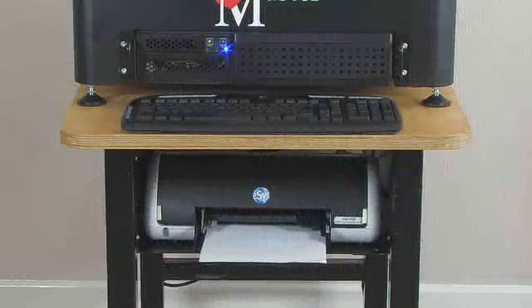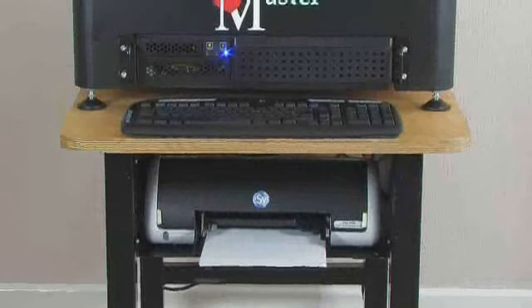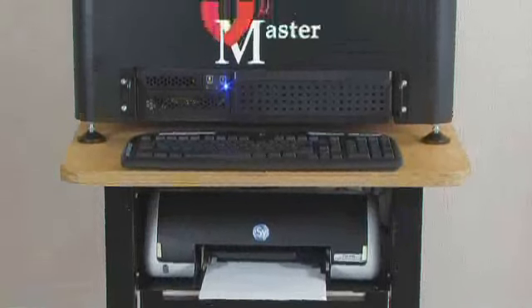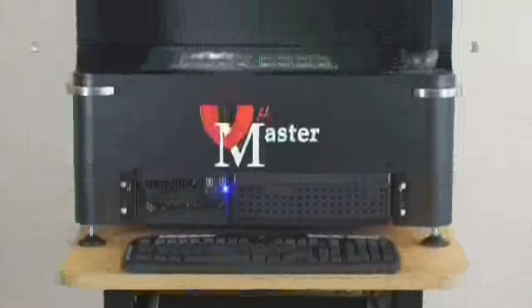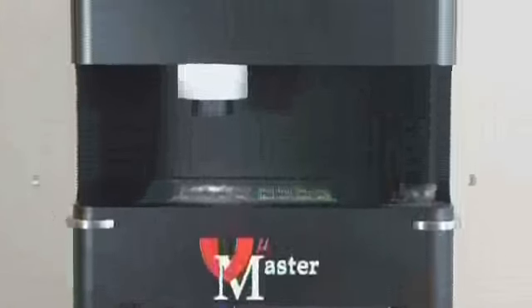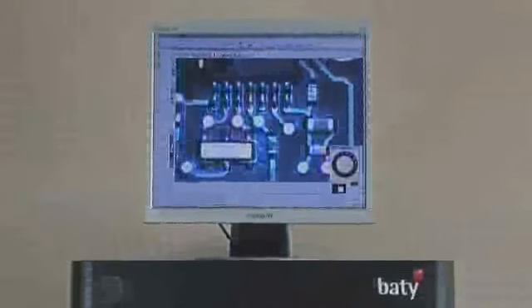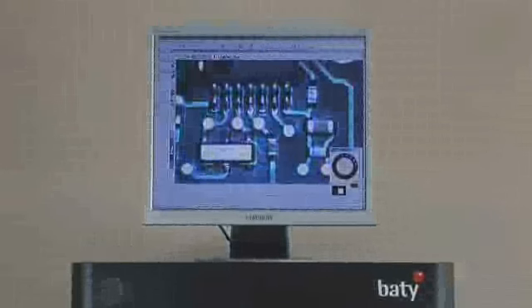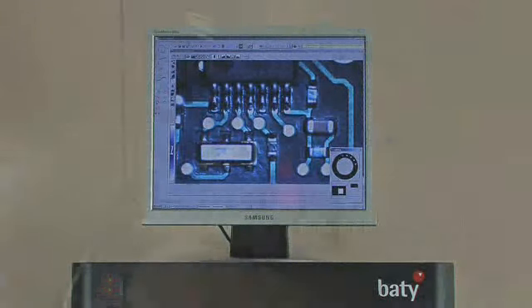Measurements and reports are made using Baty's PC-based Fusion software. The industrial PC controller is fitted into the chassis, so there is no need for cable management and additional bench space. A 19-inch LCD monitor and even a printer are also included in the standard package. Just plug in the single power cord and you are ready to measure.